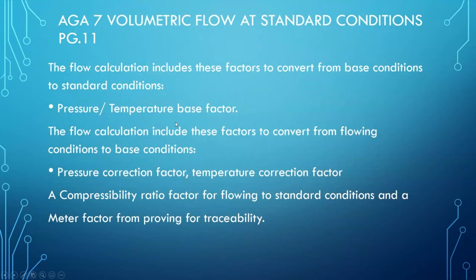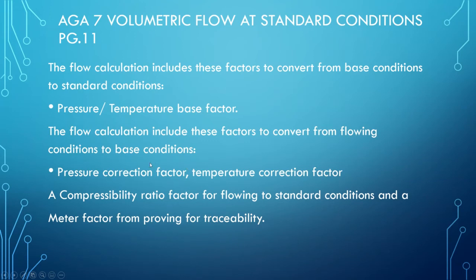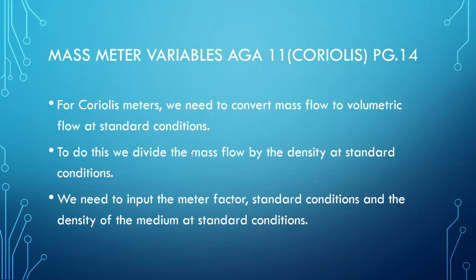AGA7 covers volumetric flow at standard conditions, as shown on page eleven. The flow calculation includes a number of factors to convert from flowing conditions to standard conditions: pressure and temperature base factors, a pressure correction factor, a temperature correction factor, and a compressibility ratio factor for flowing to standard conditions, as well as a meter factor from proving and traceability. Once it's all identified and configured, we don't have to worry about it too much after that.